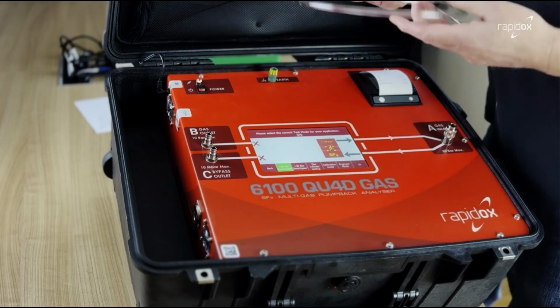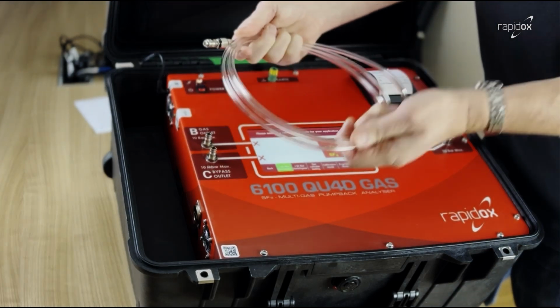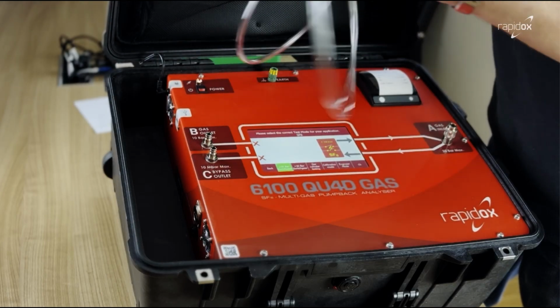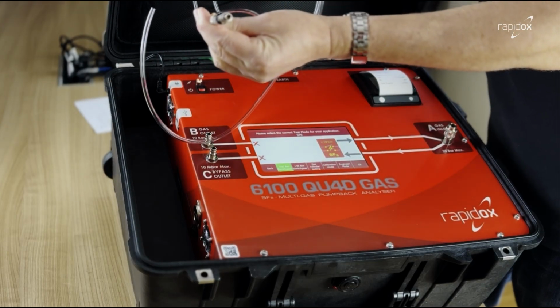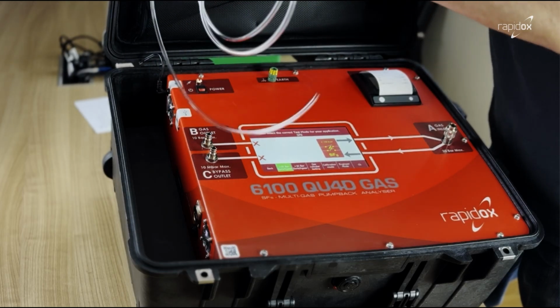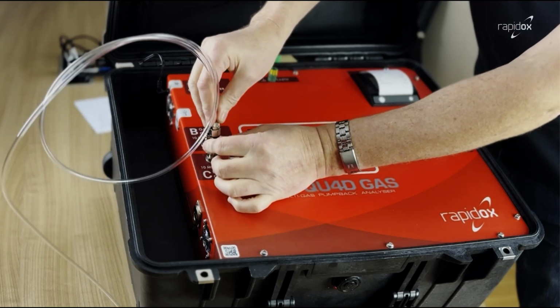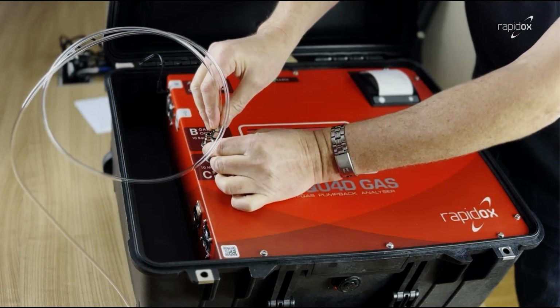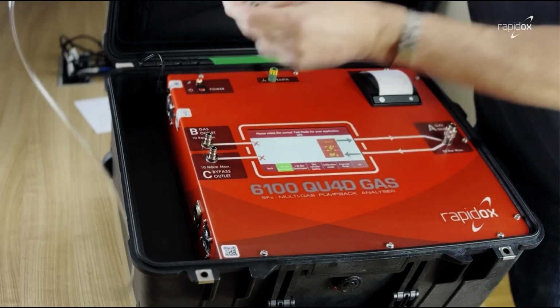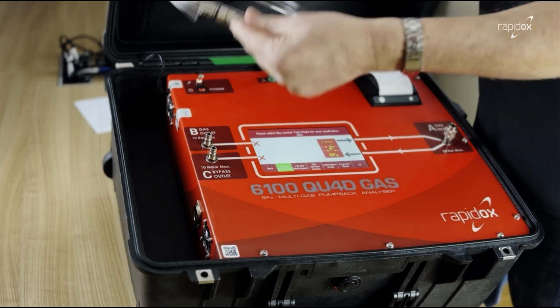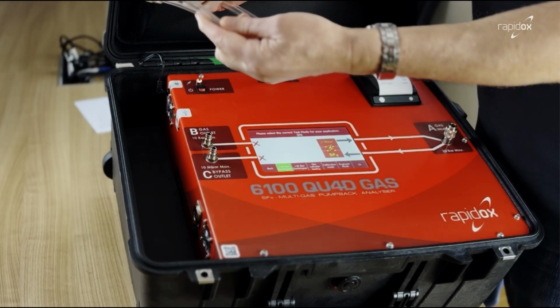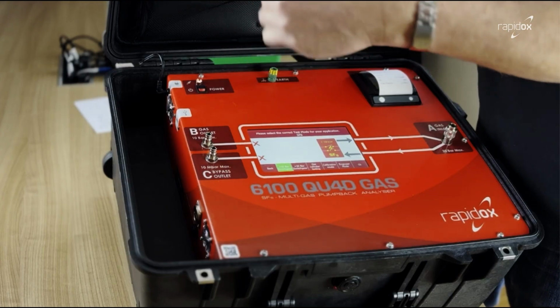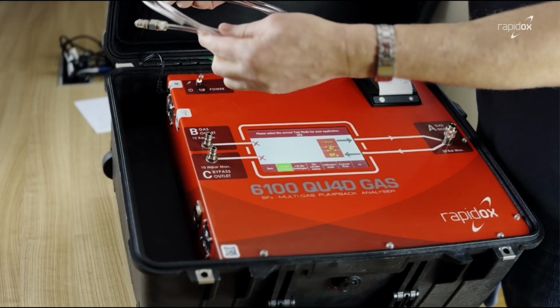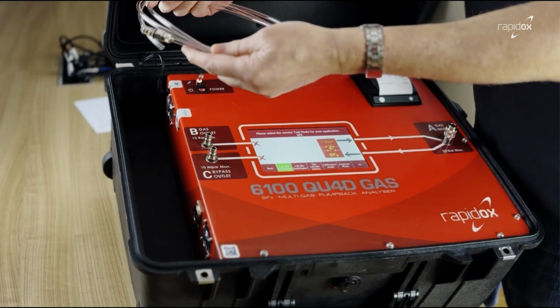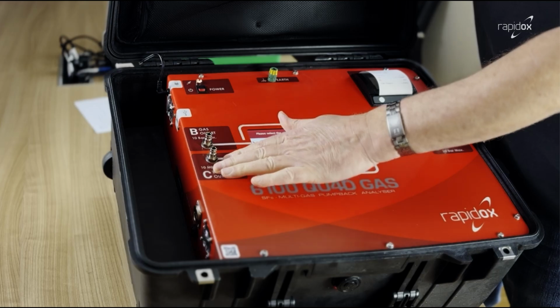Finally, we supply a tube and a connector for port C, which looks like this, polyurethane tube. And this one has a small Rectus, series 20, female. And again, it attaches in exactly the same way onto the fitting here. And when this is attached, then you will be able to run gases such as nitrogen through it to do calibration of the dew point sensor. So this apparatus is really used exclusively for calibration, testing, and occasionally if you're running the analyzer for a long period of time in continuous mode. This would normally be in a calibration testing lab. So port C is a special port that is not used very often.